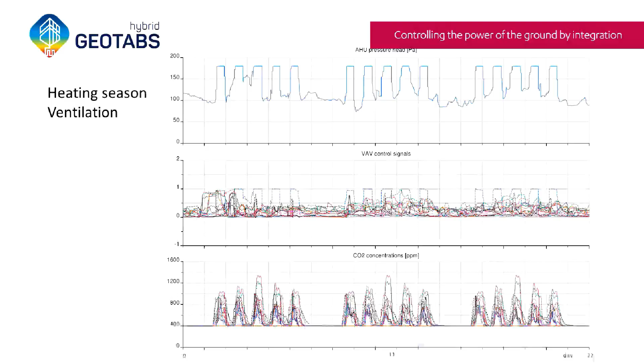This illustrates that when reaching this limit, the VAVs automatically open completely, and the supply pressure of the air handling unit goes up to the maximum of 180 pascals to push this value down as much as possible. This shows the MPC working as expected: trying to satisfy the constraint by doing whatever it can, and once satisfied, becoming more energy efficient by lowering the supply pressure and closing VAVs so the overall fan power goes down significantly.